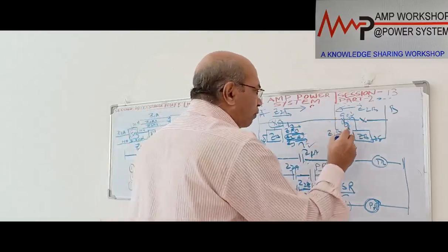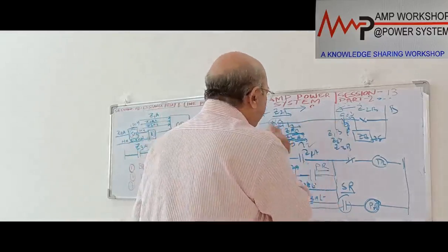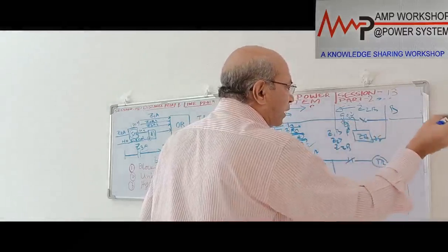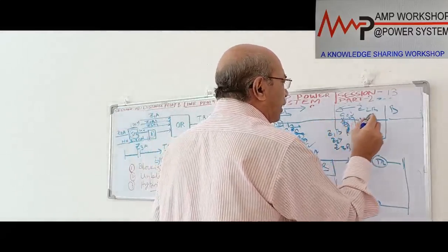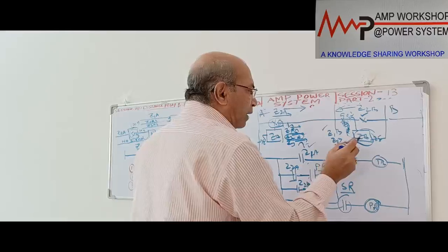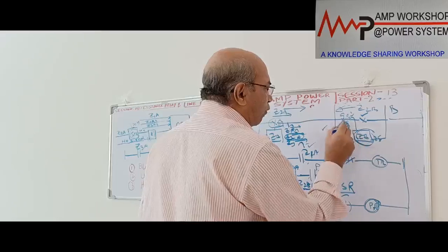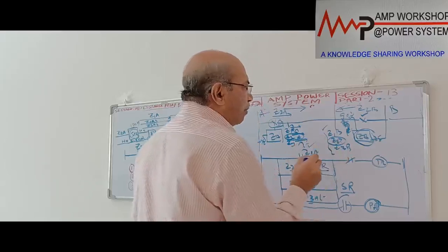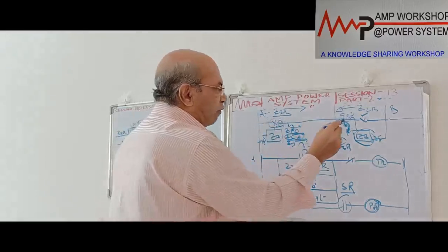So when the end zone fault, when the fault is 90% from here, in this case what will happen? This relay, it is within the Z2, and Z2 is looking up to 120% of the next line. So Z2 has operated, and when the fault is over here, immediately for this relay, what has happened? Z1 has operated, clear the fault. And at the same time, it has operated Z2 also here. When the fault is within 10%, all three elements have operated. The moment Z2 has operated, immediately it has sent a permissive signal to the other end. Okay, the fault is inside.